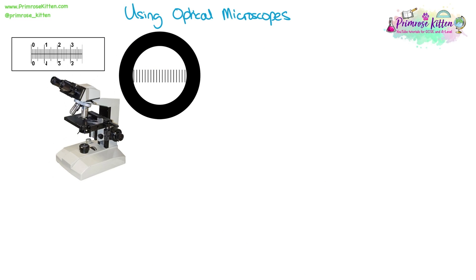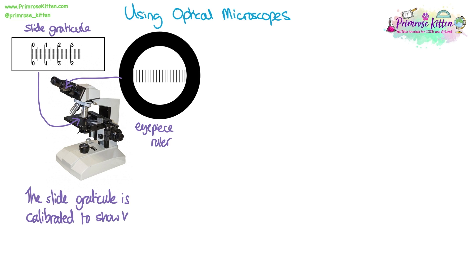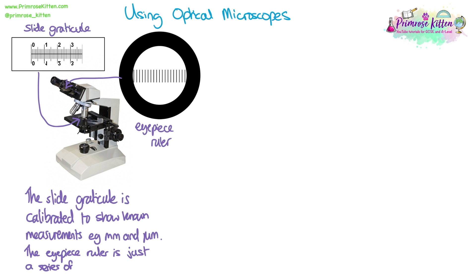There are two pieces of equipment we can use to actually measure structures in a microscope. The slide graticule is a lined ruler on a microscope slide that you place on the stage — it is calibrated and shows known measurements including millimetres and micrometres. The eyepiece ruler is a series of lines scratched into or laid onto the eyepiece lens, allowing you to lay it over structures and measure them as a scale. We call these lines eyepiece units, or EPU for short.